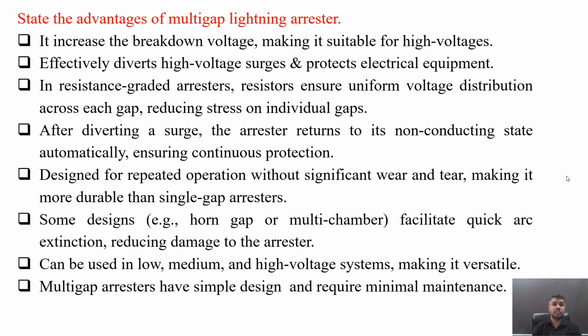State the advantages of multi-gap lightning arrestors. It increases the breakdown voltage, making it suitable for high voltages. It effectively diverts high voltage surges and protects the electrical equipment to which it is connected. In resistance graded arrestors, resistors ensure uniform voltage distribution across each gap, reducing stress on any individual gap. After diverting a surge, the arrestor returns to its non-conducting state automatically, ensuring continuous protection and making the lightning arrestor ready for another operation.